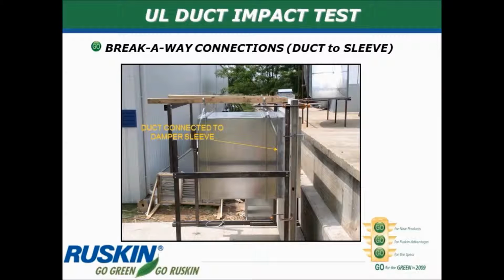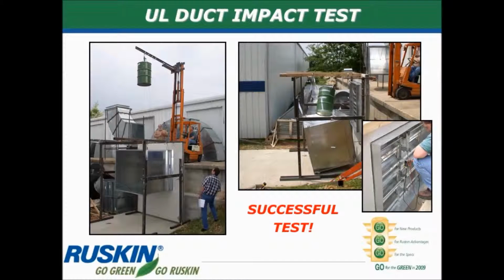So to make sure that happens, we have what are called breakaway connections. The ductwork connected to the damper sleeve must be able to break away if something collapses onto it and still leave the damper in place in the wall. And there is an actual UL rated duct impact test where a damper and its sleeve are installed in a wall. They build a mock-up wall, install a damper in it, have ductwork connected to that damper sleeve, and then they take a 55-gallon drum and fill it with sand to the prescribed weight. They raise it up a certain distance above the ductwork, and then they drop it. And it slams down on that duct, and that duct must break away from the damper sleeve.